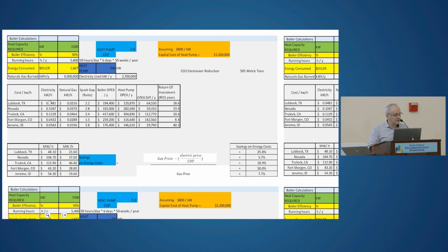So you take the electricity rates in the different locations you get, Texas, Nevada, California, Colorado, Idaho, the electricity price, the natural gas price, and then your spark gap ratios. Then you have the operation of that boiler per year, how much you spend annually on that energy, and on the heat pump, the difference between those two energies. Then you divide that CAPEX by this OPEX, and it gives you the return in years.